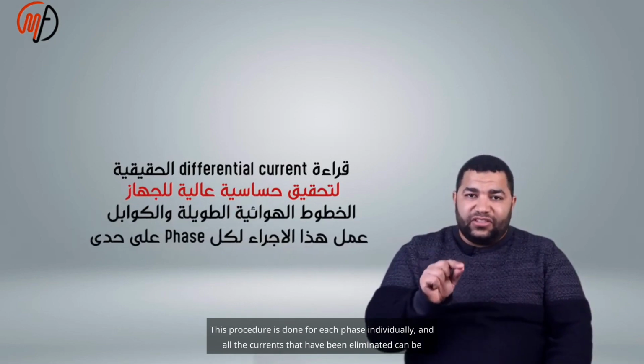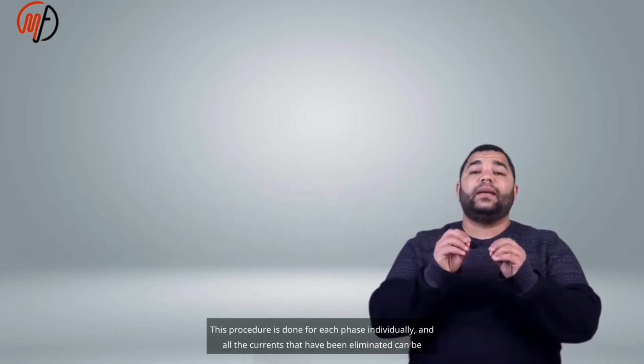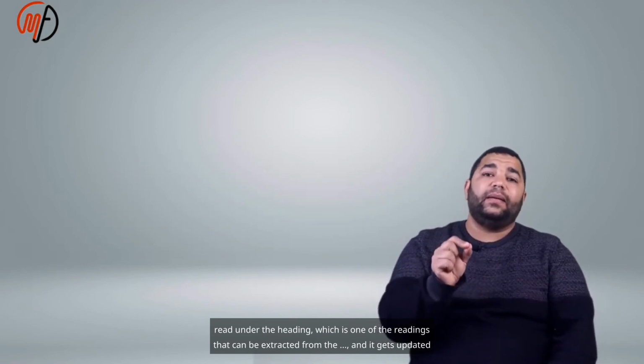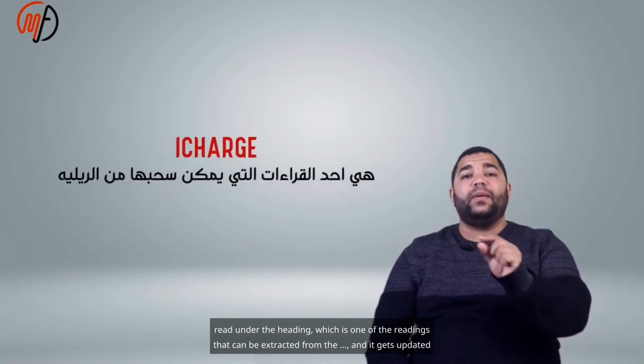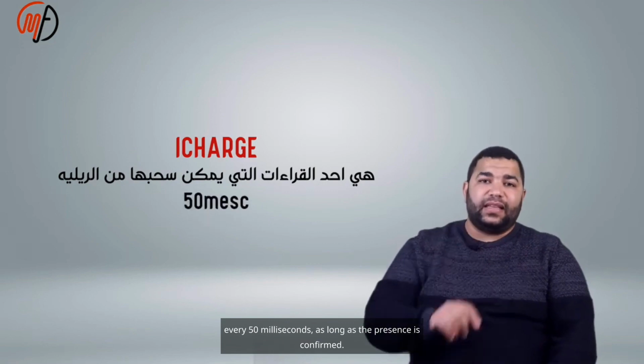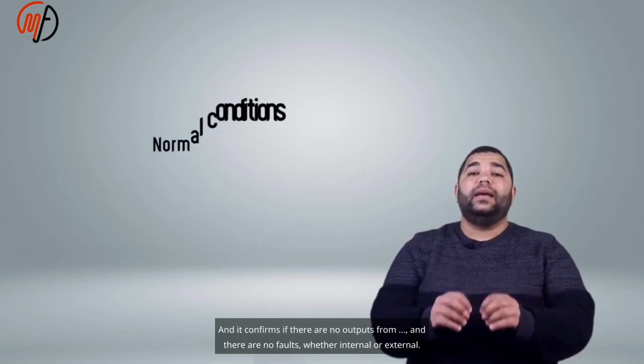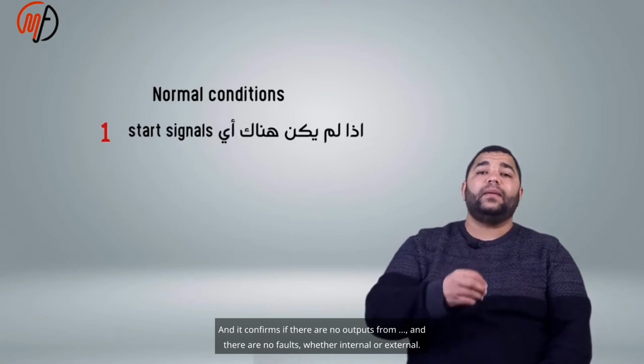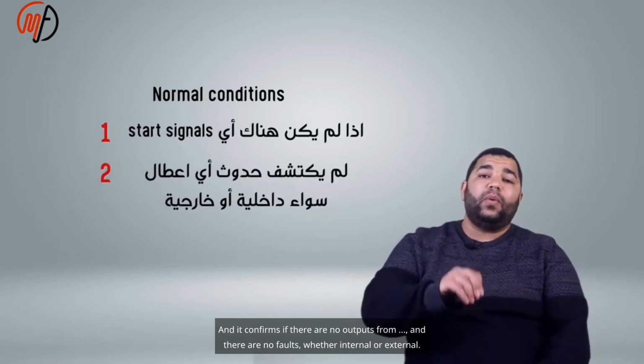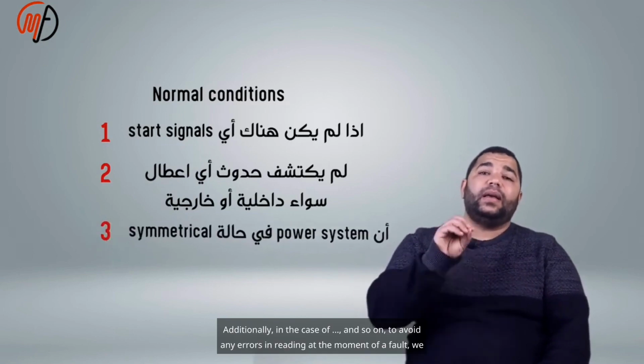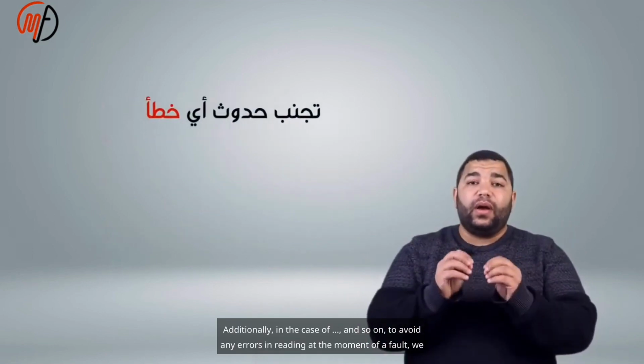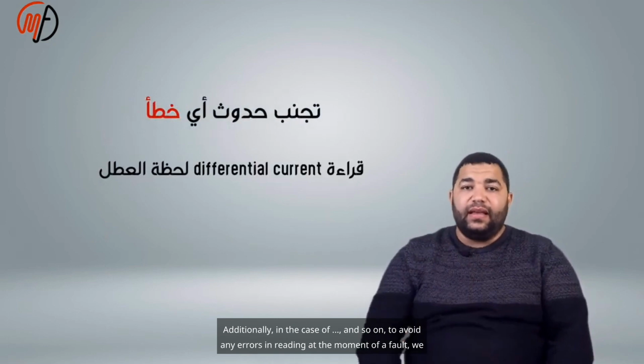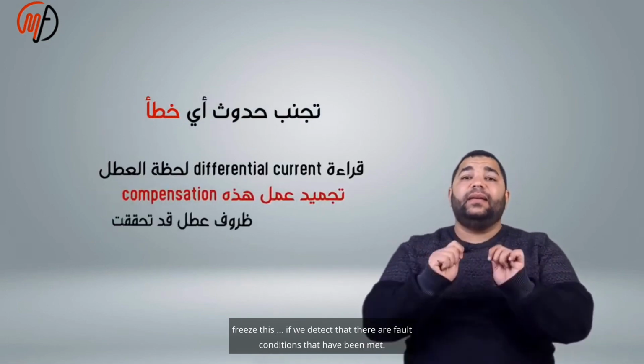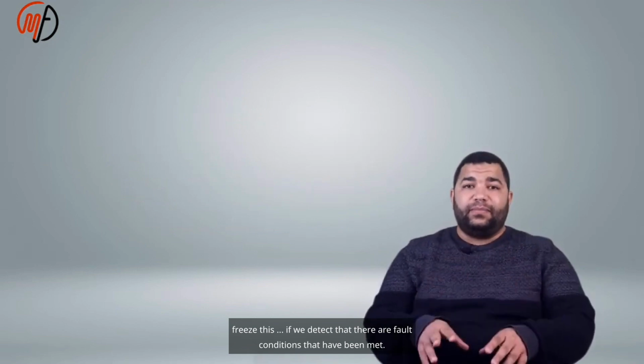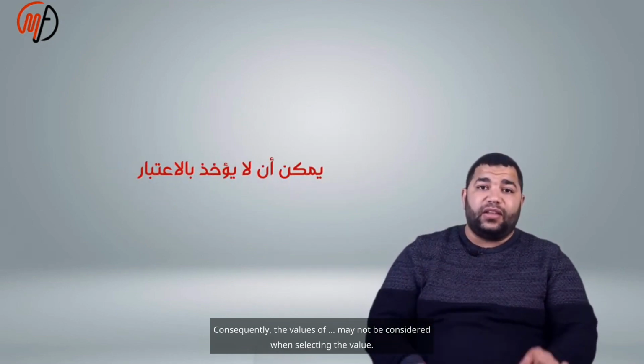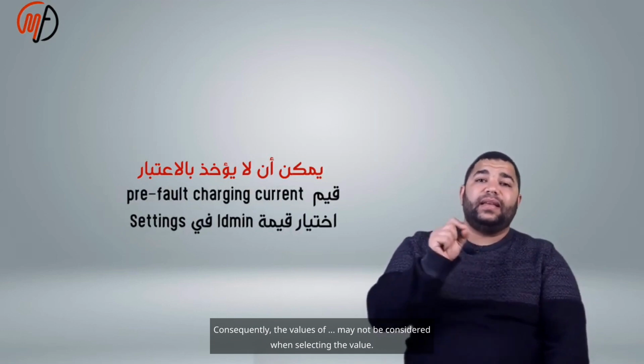This procedure is done for each phase individually, and all the currents that have been eliminated can be read under the heading, which is one of the readings that can be extracted from the device, and it gets updated every 50 milliseconds, as long as the presence of the voltage is confirmed. And it confirms that there are no outputs and there are no faults, whether internal or external. Additionally, to avoid any errors in reading at the moment of a fault, we freeze this value if we detect that there are fault conditions that have been met. Consequently, the values may not be considered when selecting the value.